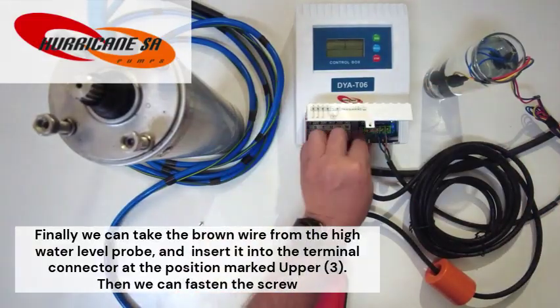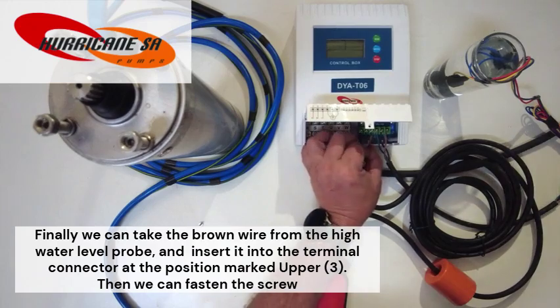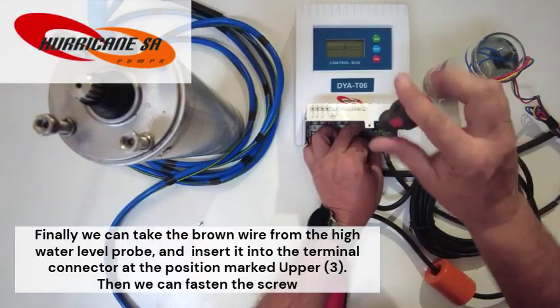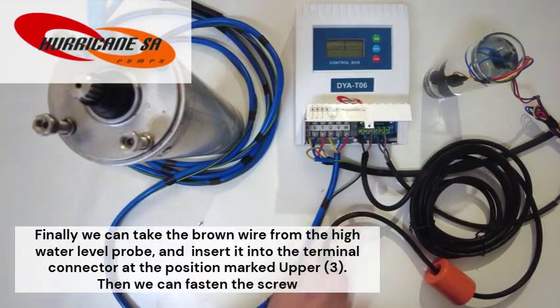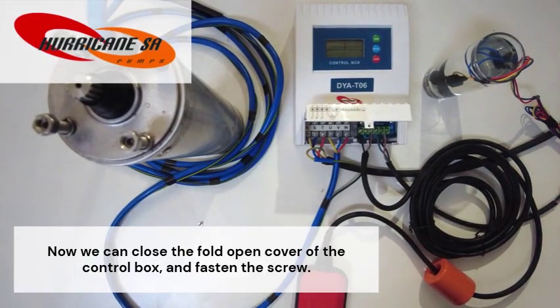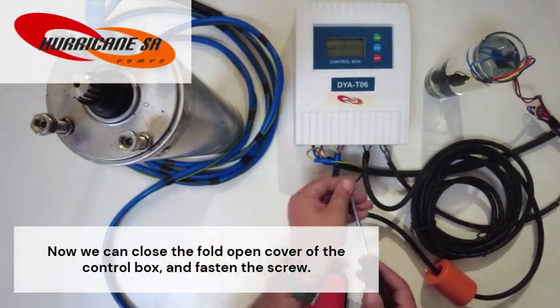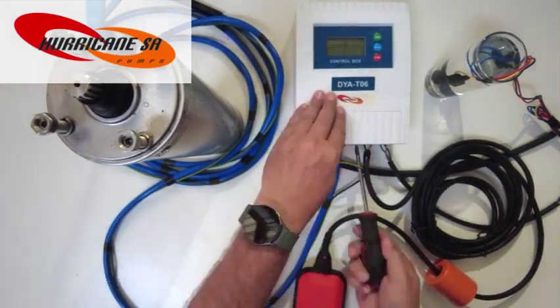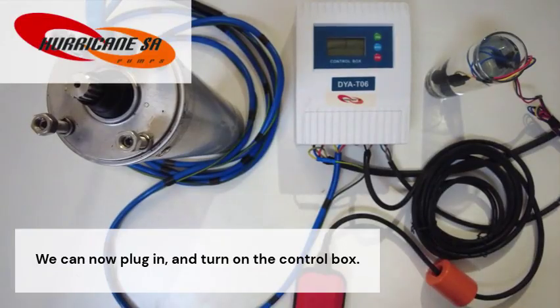Finally, we can take the brown wire from the high water level probe and insert into the terminal connector at the position marked upper 3. Then we can fasten the screw. Now we can close the fold open cover of the control box and fasten the screw. We can now plug in and turn on the control box.